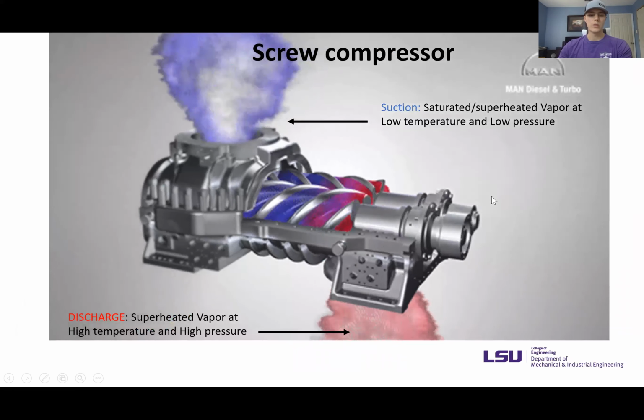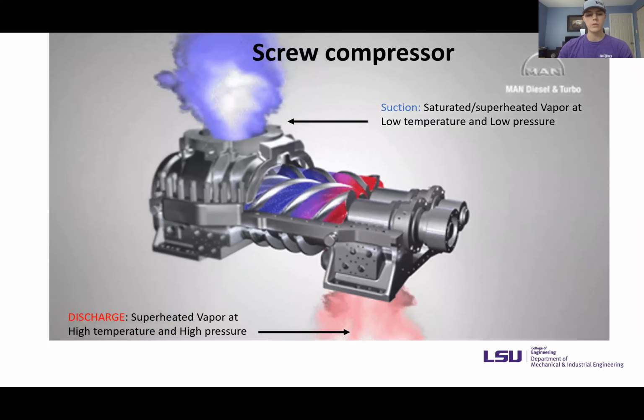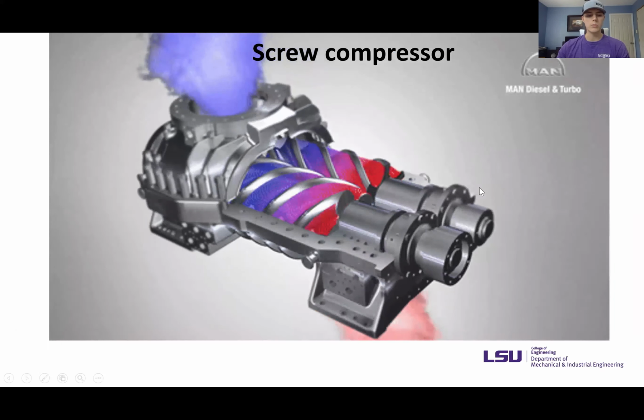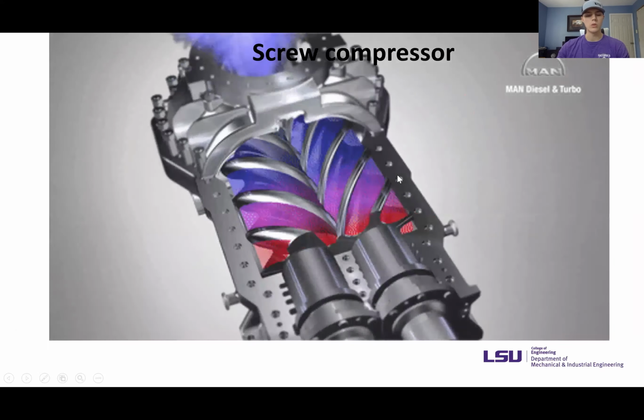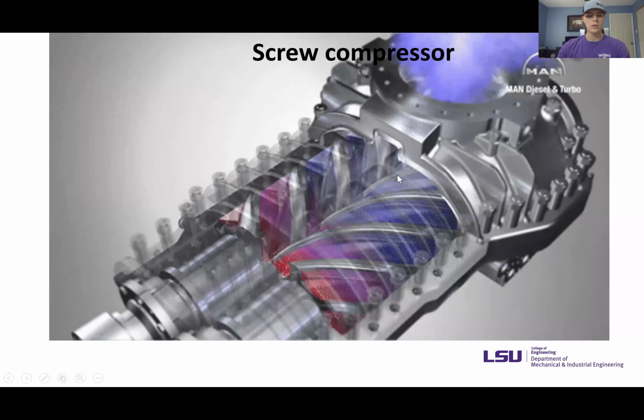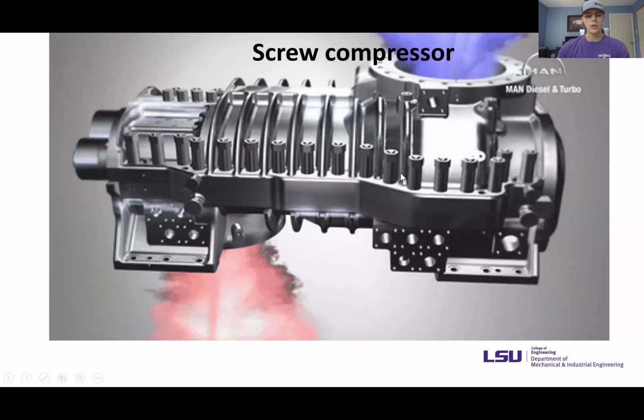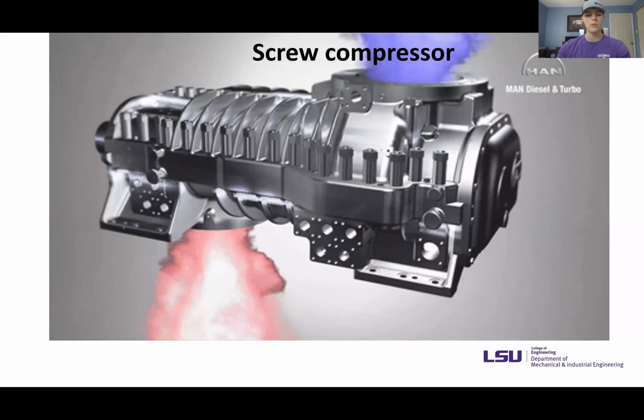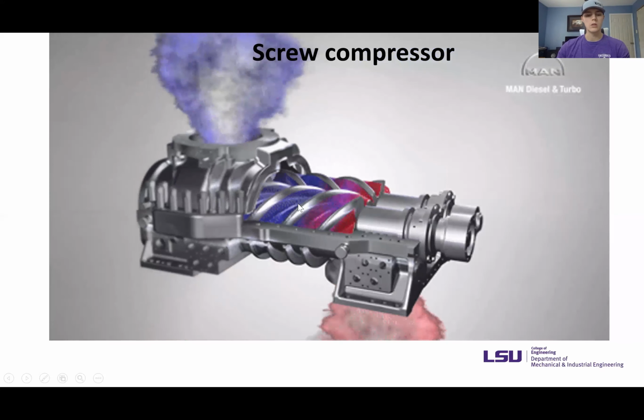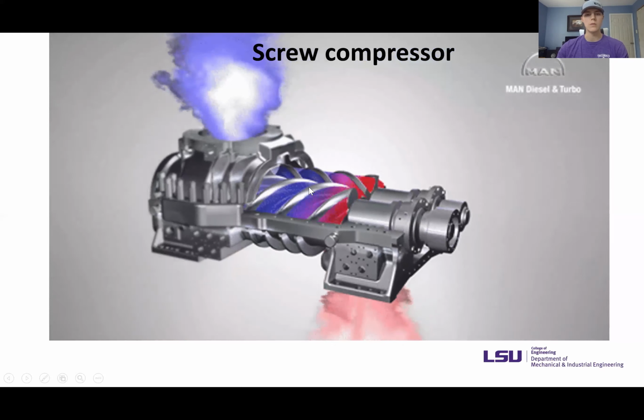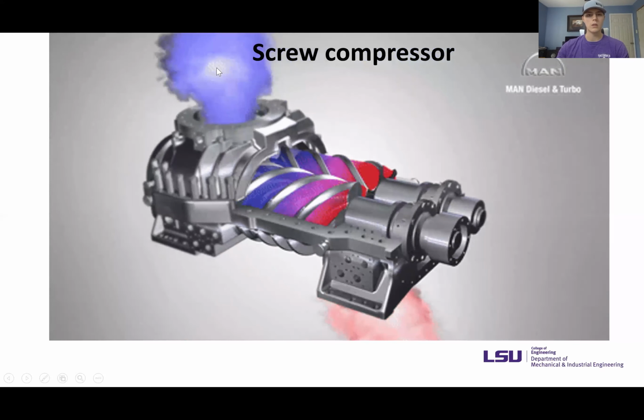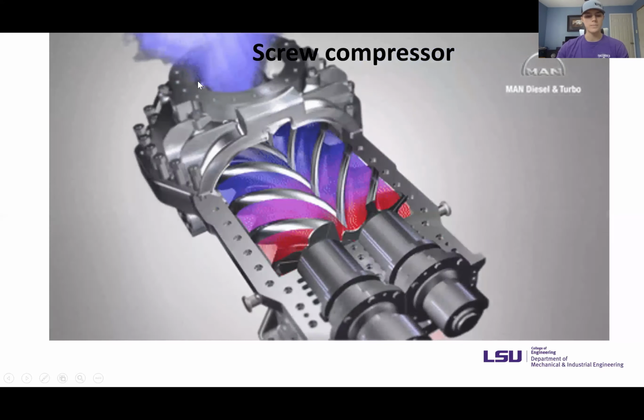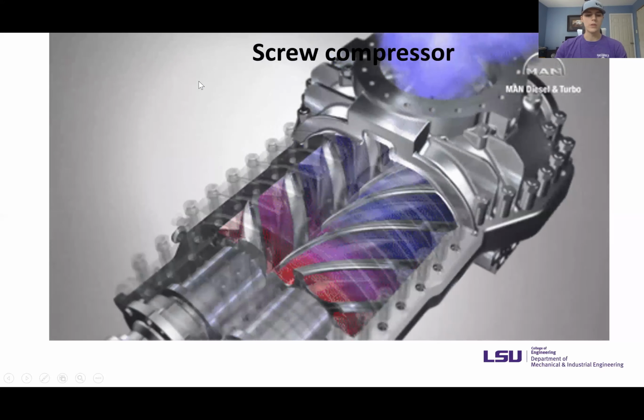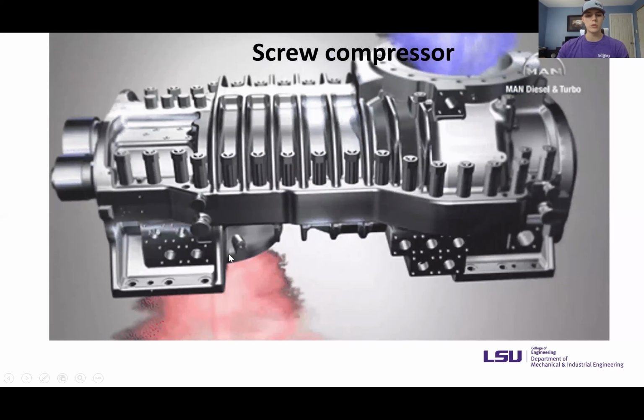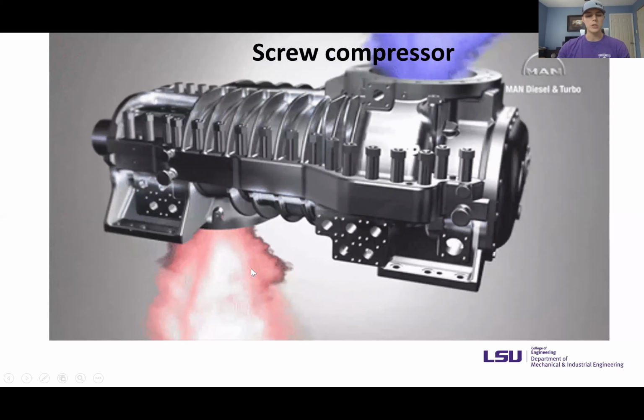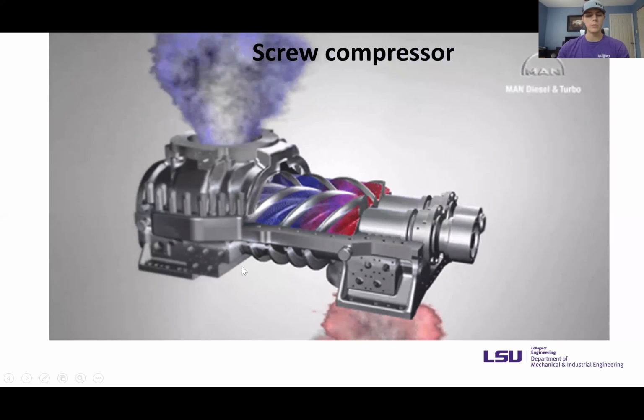So the screw compressor is the driving force of the refrigerant. It's run by an electric motor and uses single or multiple rotors. Refrigerant enters on the suction port as a low pressure, low temperature saturated vapor, or for some compressors, it'll enter as a superheated vapor. That's going to be indicated on the blue gas right here. And the refrigerant exits at the discharge port in red as a high pressure, high temperature, superheated vapor.